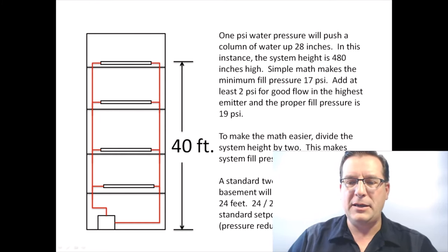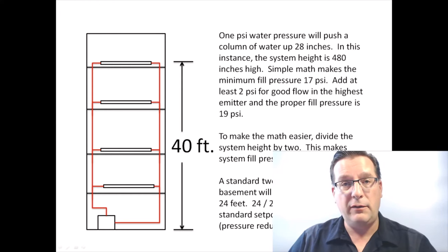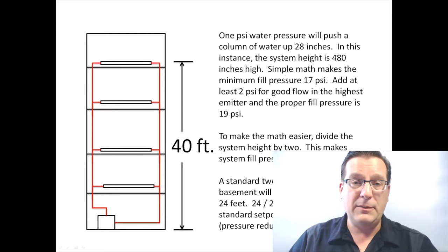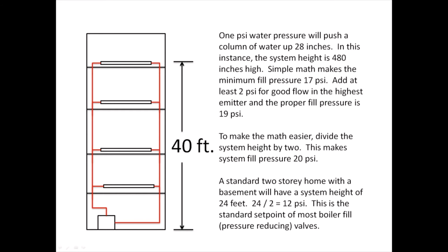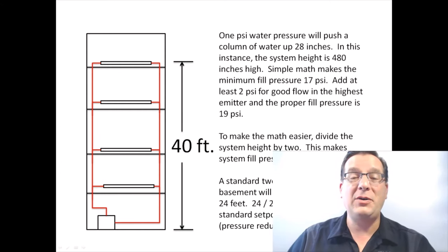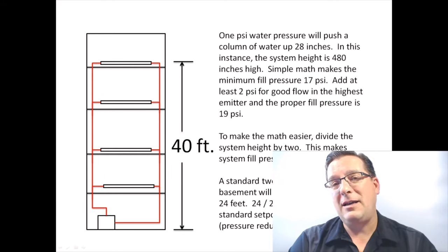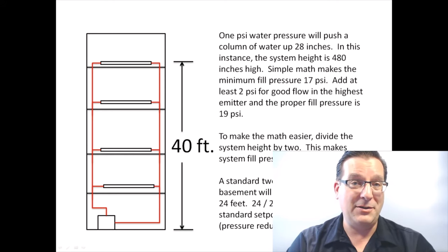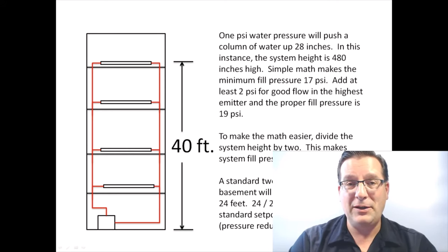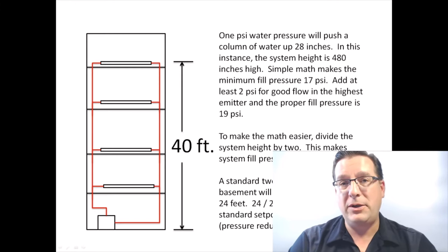If you buy a pressure reducing valve out of the box, back in the old days these used to come set at 12 PSI. Why? Because a standard two-story home with a basement has an average maximum height of about 24 feet, and 24 divided by 2 is 12 PSI. Nowadays, pressure reducing valves have started to come preset at about 15 PSI, likely because it's the style today to build taller houses with higher ceilings, and that's reflected in the standard pressure reducing valve set point.